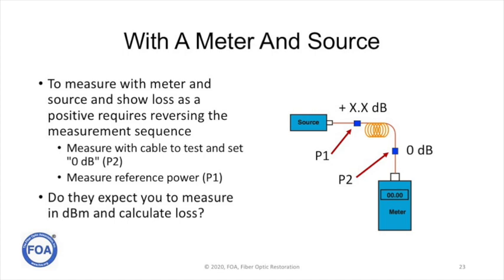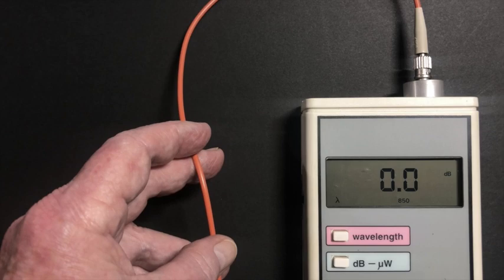If you want to measure with a meter and source and show loss as a positive reading, you have to reverse your measurement sequence. You have to start by making the complete system, launch cable, cable to test and receive cable, and measuring that and setting 0 dB, then going back and measuring the output of the launch cable. That way your output of the launch cable is a bigger number and you get a plus reading. But how many people measure that way? The typical way to measure is you set the output of the launch cable and you go test cables and you can keep testing cable after cable, fiber after fiber, and making loss measurements to that reference. Theoretically, if you did it this way, you would have to make a reference measurement after every test.